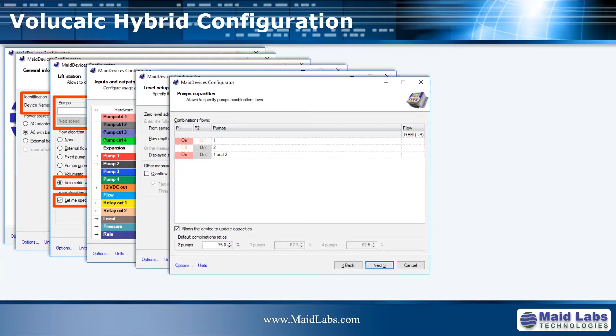Then you enter the dimensions of the well and specify what alarms you want the instrument to detect automatically. Examples: the level drops without any pump running, that's not normal. A pump doesn't alternate even for one cycle, that's not normal, it should. Or the capacity of the pump has changed, since we calculate drawdown every cycle, it's easy for us to detect this.